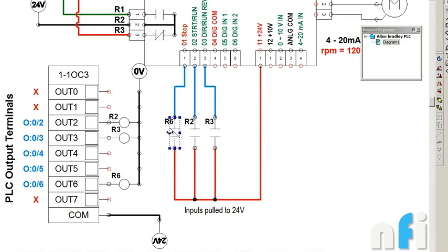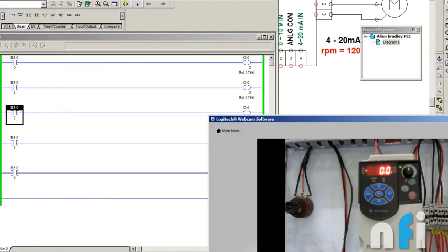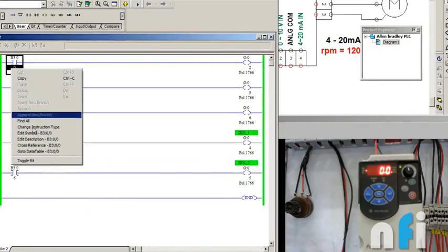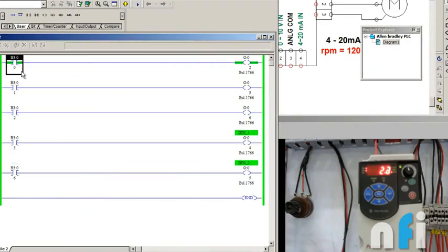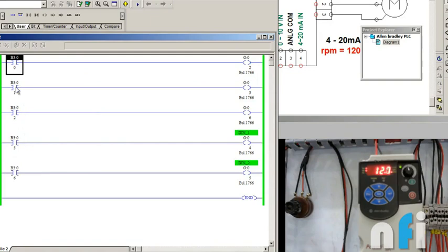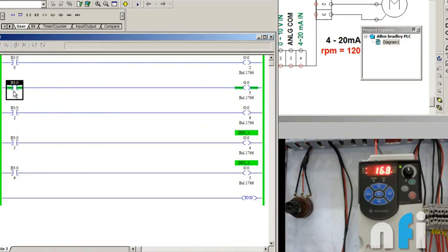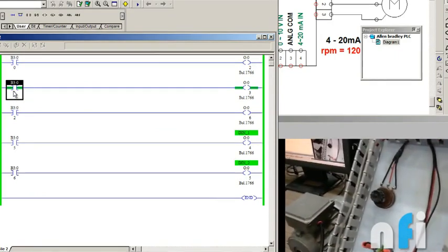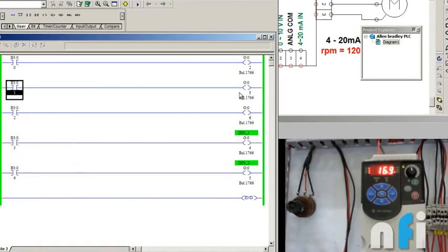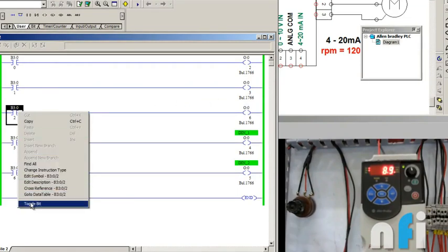When 11 and 2 gets connected, drive will start. It will push to start, it will latch itself. When 11 and 3 gets connected, drive will change the direction. Let's see the change in direction now. Right now I have to start it once. As I started the drive, to change the direction I have to start this one. When I run this one, drive will go to reverse. And see, it will go to reverse. It's the motor. To make it forward again, I will turn off the OUT3. I will go back to forward. To stop the drive, I have to run it once as well. Stop the drive.